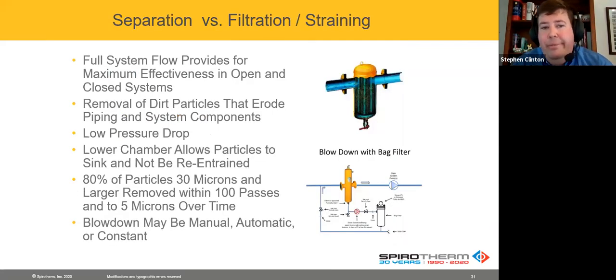And how are we different? Well, in our case, we're looking at full flow. What you're seeing here is a dirt separator, a dirt-only separator. It's exactly the same unit as the air and dirt separator, but there's no air removal side. So we're using the same principles: reduce the velocity, reduce the turbulence, let the dirt particles bounce around and let gravity pull them down. The other thing that's important is we separate. We don't filter, we don't strain. If you filter and strain, you get a high pressure drop initially, and it grows and gets greater the more it loads up.